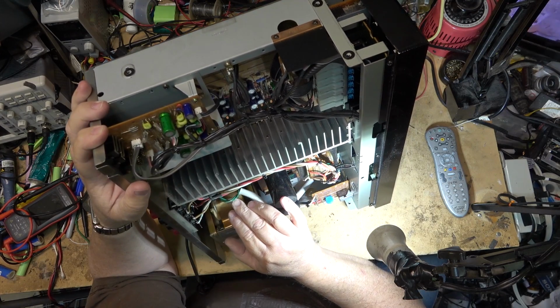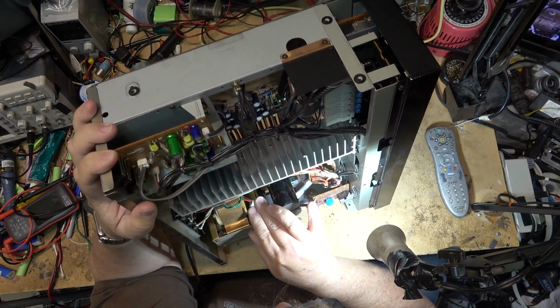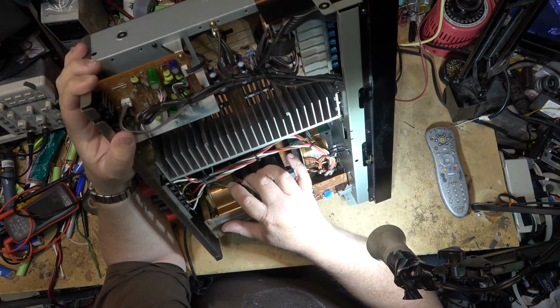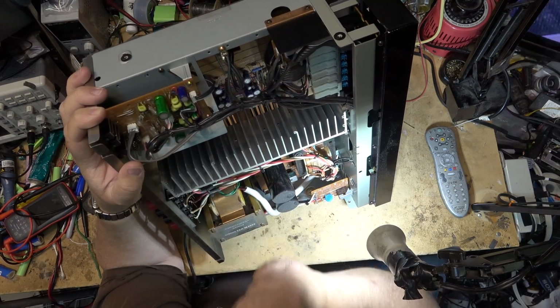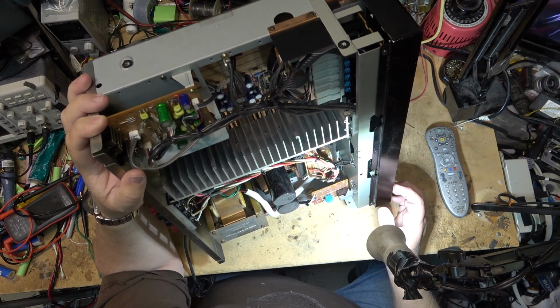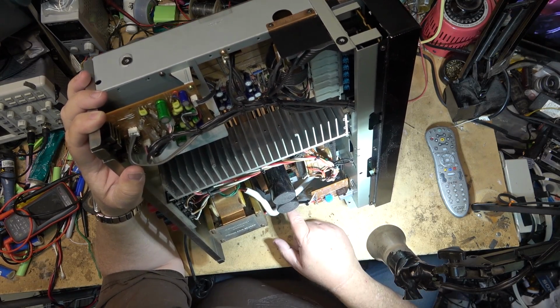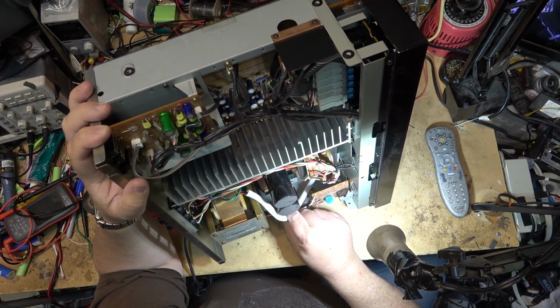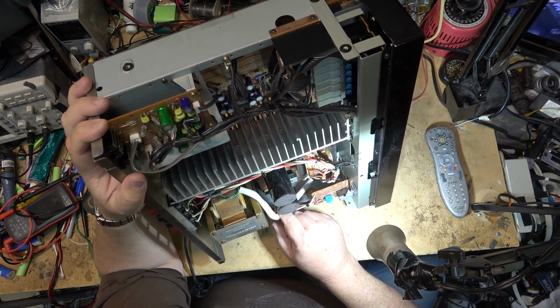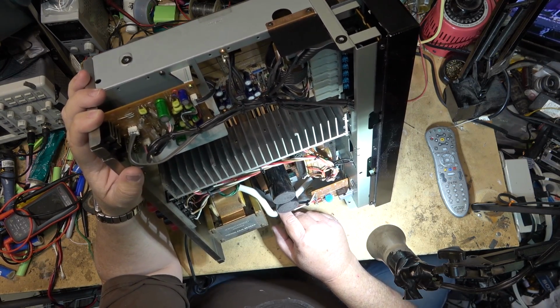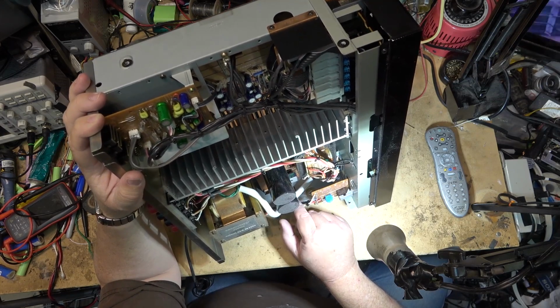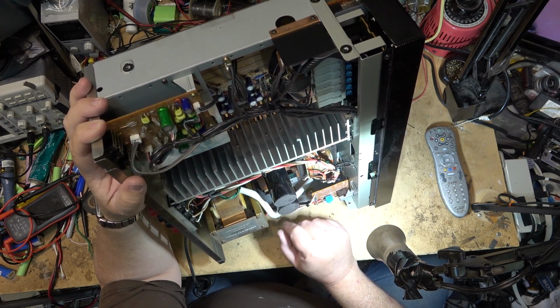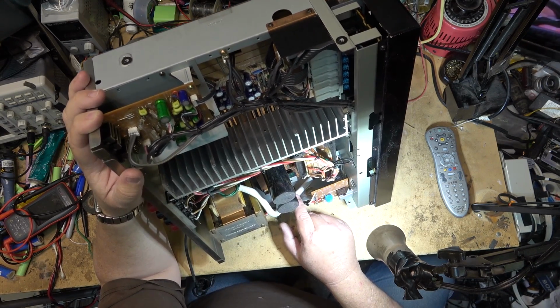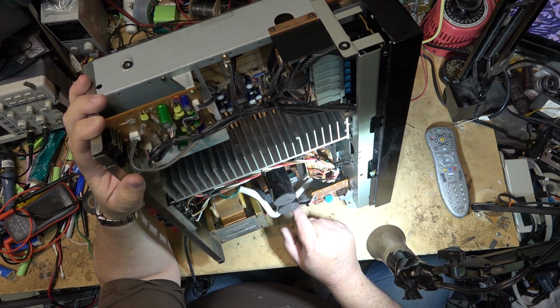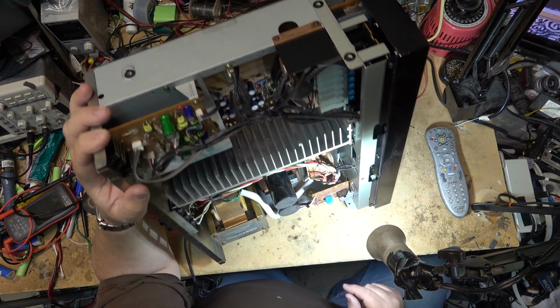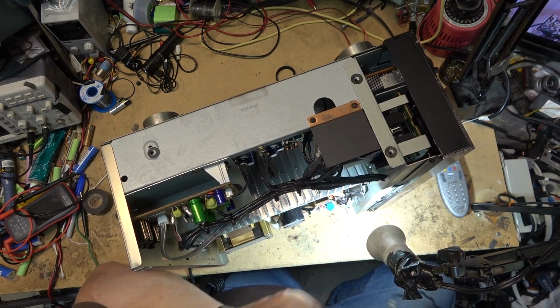Yeah, it's got a center tapped output and a straight output. So what I can do is disconnect the secondary and measure. I can run it on 120 and measure what the voltage is, and it will be half. Or I could give it 240 and measure the voltages on here, and see if I can find a transformer with a similar output.